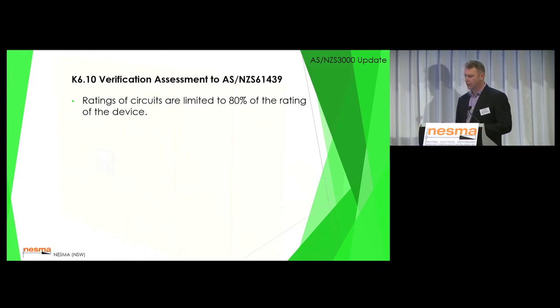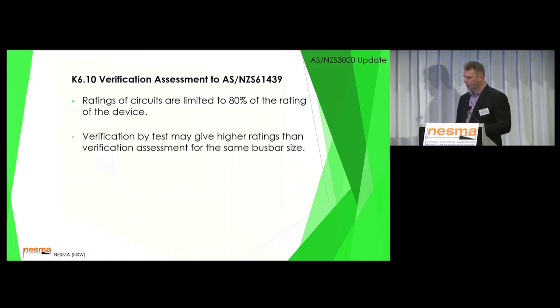The ratings of the circuits are limited to 80% of the rating of the device. So what you must understand is if you've got a 250 amp breaker and you're going to provide a temperature calculation, you can't go past 200 amps for the rating of that breaker. That may give you better results on your rated diversity, but you can't go past that derating. Verification by test may give you higher ratings than the verification assessment for the same busbar size as well.